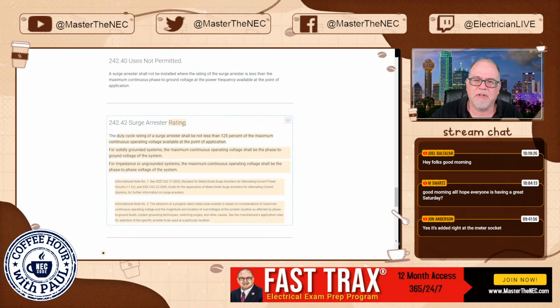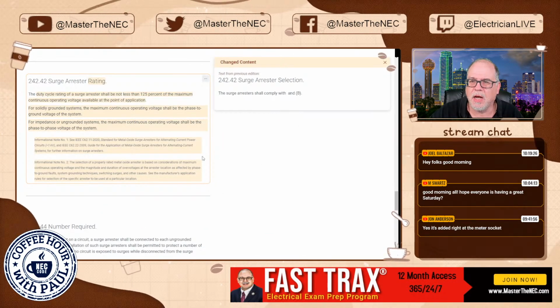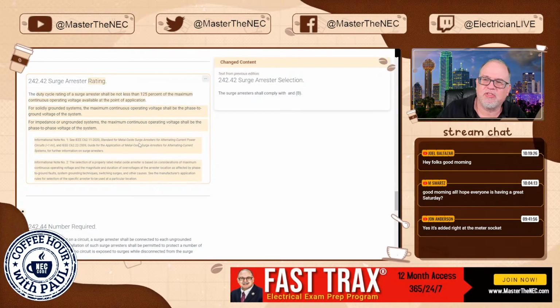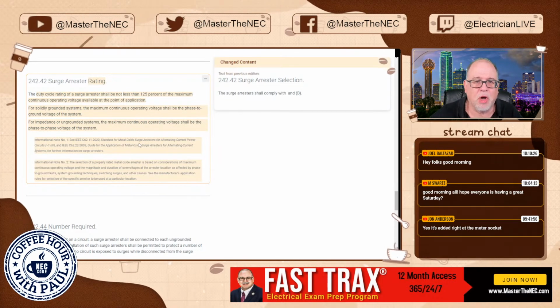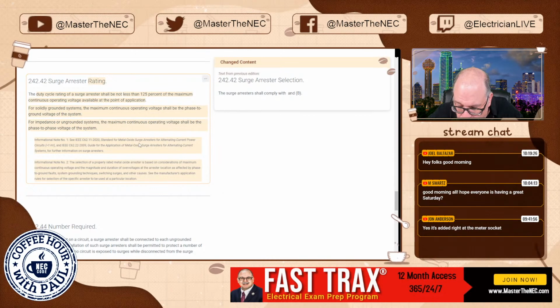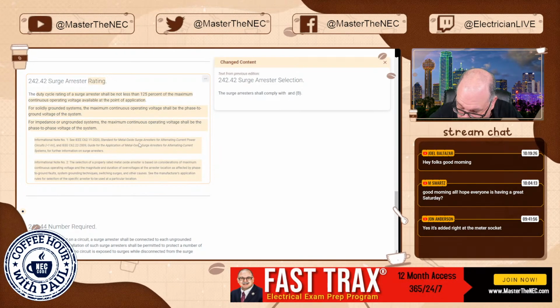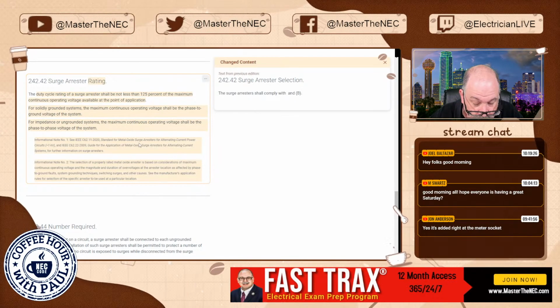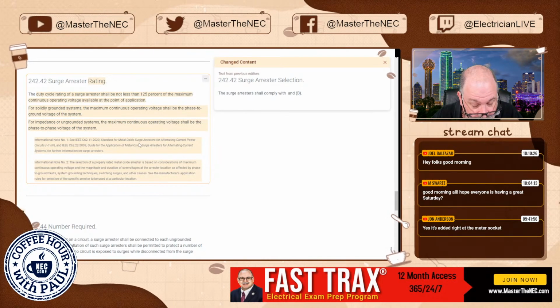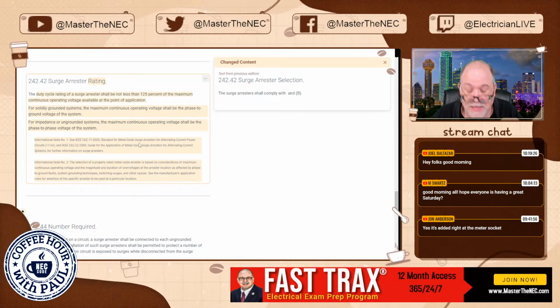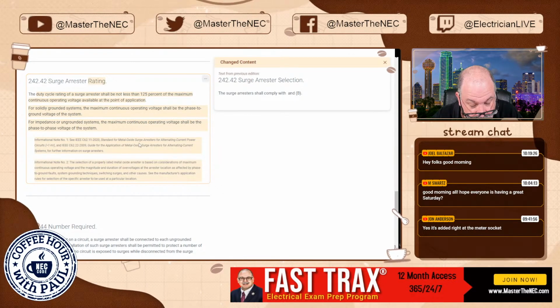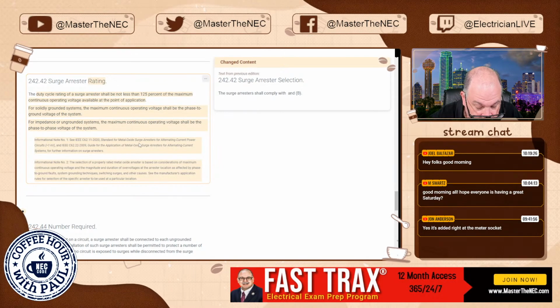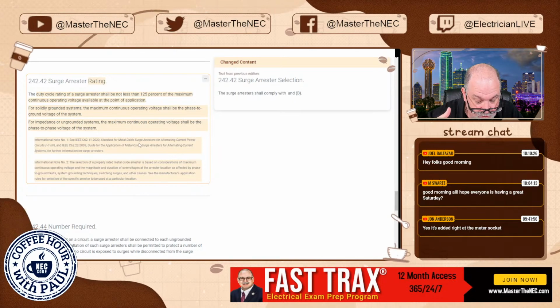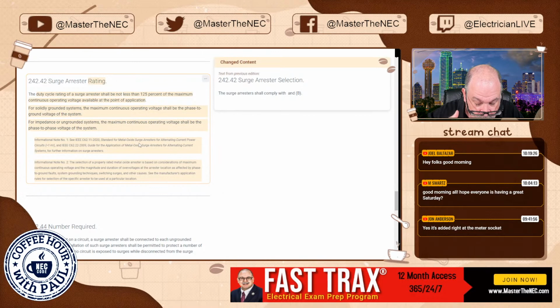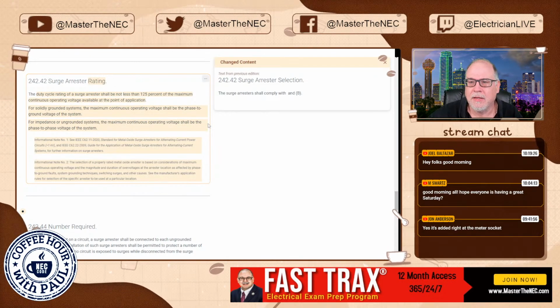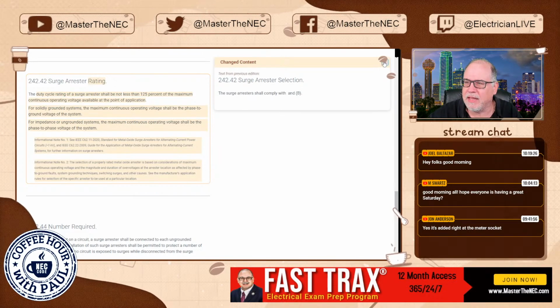Now, surge arrester rating, 242.42. This was in the code before. It just says surge arresters shall comply with, blank, and B, right? If you go look at the code, I'm going to look at my code book, at 242 and see what it said for 242.42. It said surge arrester selection, and then it said rating, well, actually it was A and B. The A was the ratings, and then, of course, you had solidly grounded system, impedance or ungrounded systems. And then you have B, which is silicon carbide types of surge arresters. So anyway, instead of doing that A, B, all that, all they did was combine it in one.